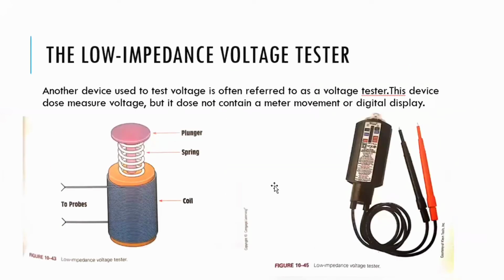Okay, this is another type of voltmeter. We can measure the volt. This is called the low impedance voltage tester. Another device used to test voltage is often referred to as a voltage tester. This device does measure voltage, but it doesn't contain a meter movement or digital display. Instead, it uses a plunger.